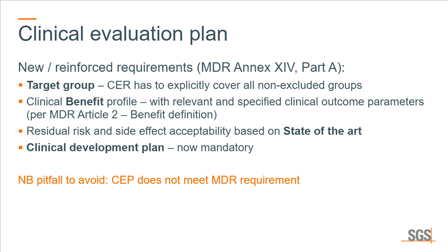The second one is the clinical benefit profile with relevant and specified clinical outcome parameters, because now under MDR Article 2, the benefit of the device is defined. And I am going to talk a little bit more about benefit in the next slide. The residual risk and side effect acceptability should be based on the state of the art. So basically, you will need now to look at your device in the context, not just by itself.